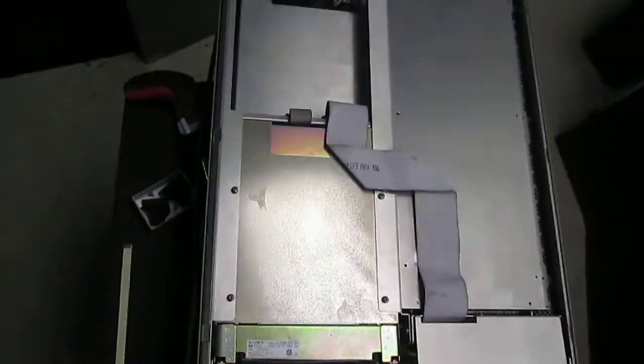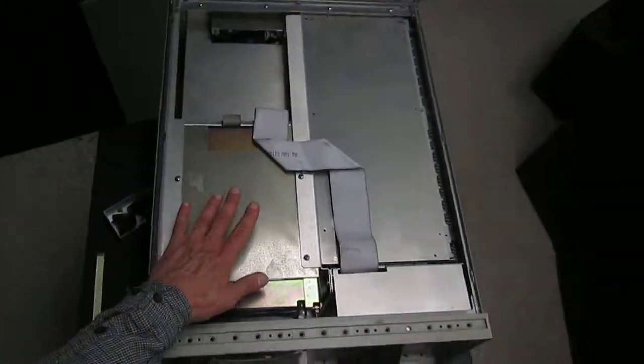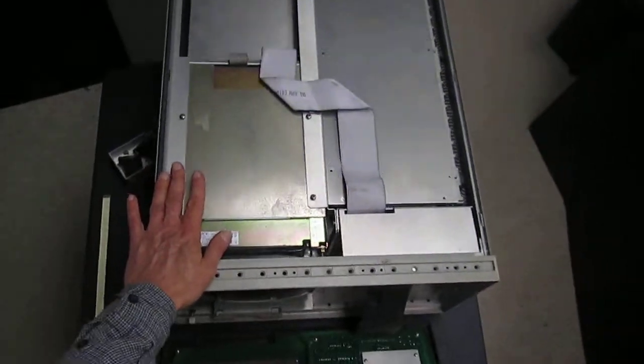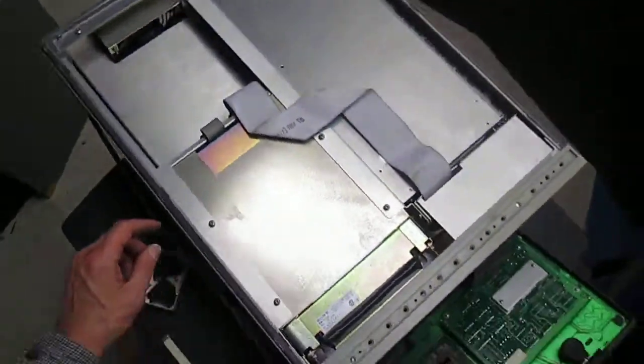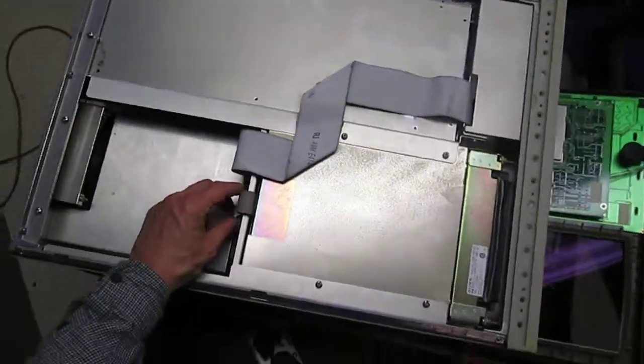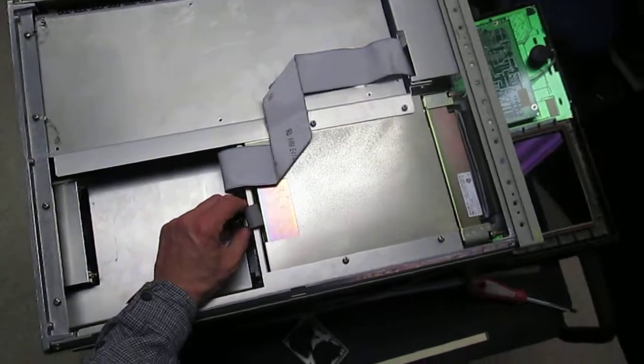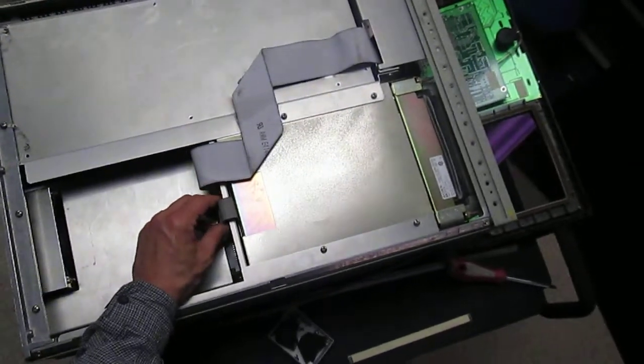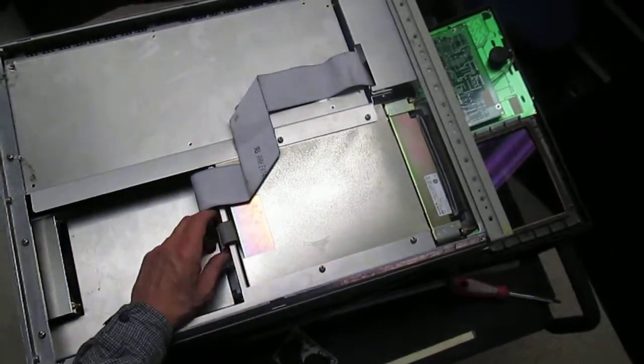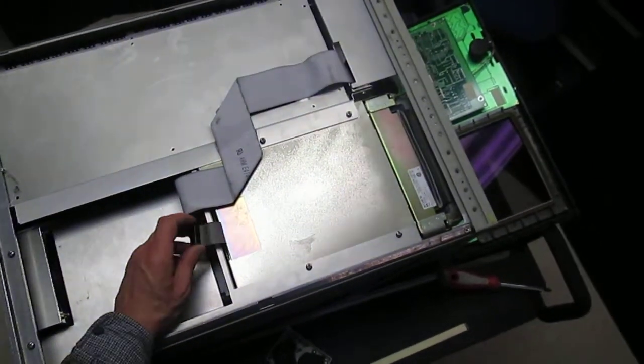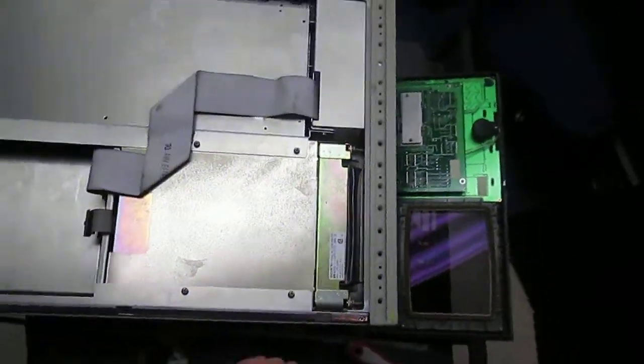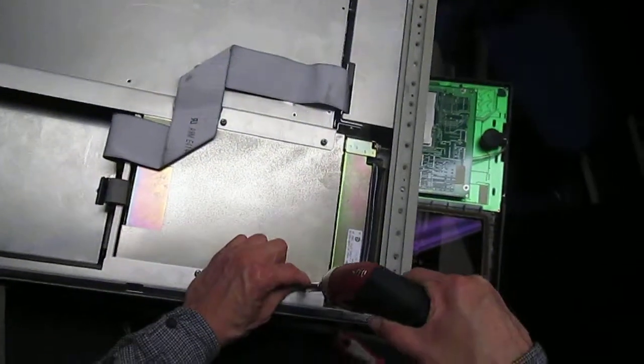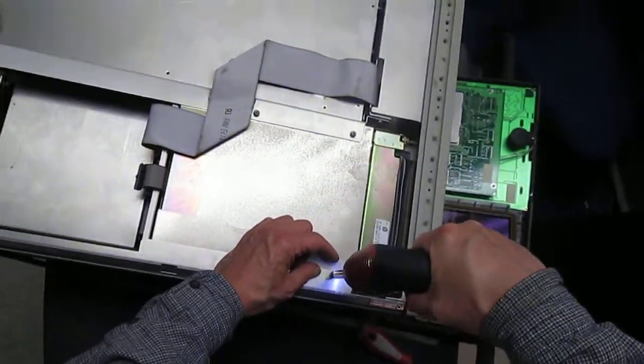Now you're ready to remove the four screws that hold the display in place. But first, let's just disconnect the display from the analyzer. It's just one IDC ribbon cable connector. Now the display is disconnected, and we remove the screws.